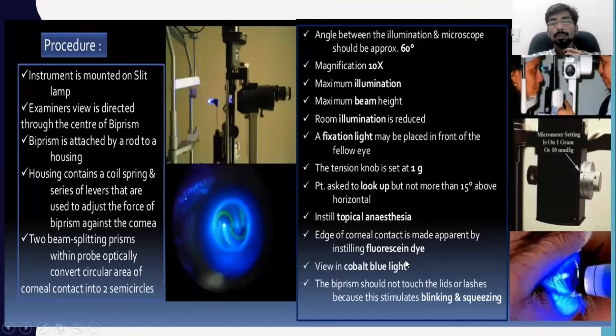Edge of the corneal contact is made apparent by instilling fluorescein dye, in cobalt blue light, and the biprism should not touch the lids or lashes because they stimulate blinking and squeezing. Patient should blink the eyes once or twice to spread the fluorescein stained tear film over the cornea. Then keep the eyes open wide. Should not apply any pressure on the globe because this raises the IOP. In some patients, hold the eyelid open with thumb and index finger of one hand against the orbital rim.